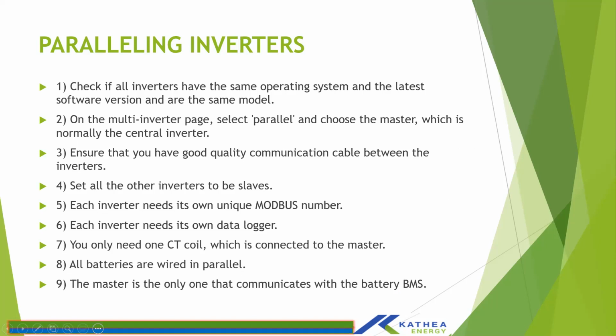So as I've said, each inverter needs a unique Modbus number, and each inverter needs its own data logger. Each inverter would upload data on its own to the server, so each and every inverter has to have its own data logger. But the CT meter, you'd only need one CT meter per phase, on a single phase, that you connect to the master inverter. The data logger, each inverter has to use its own, but the CT, you only need one that will be connected to the master.